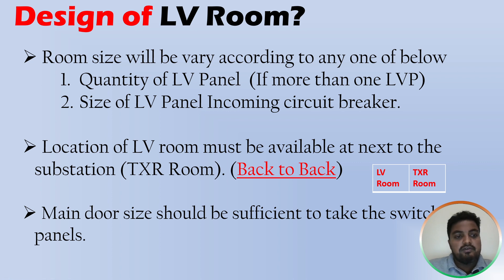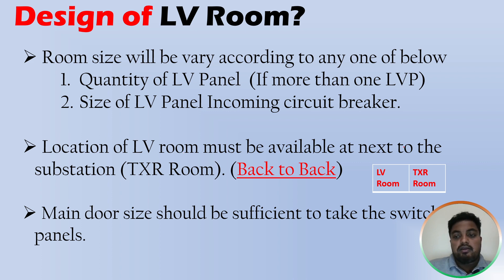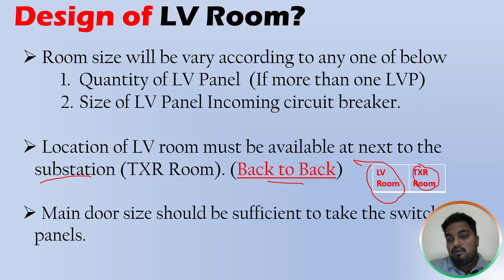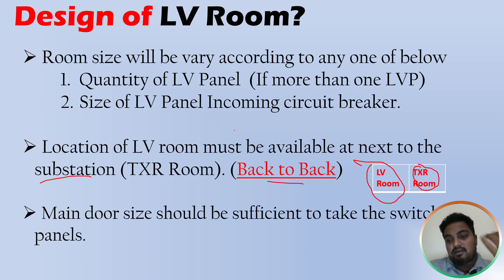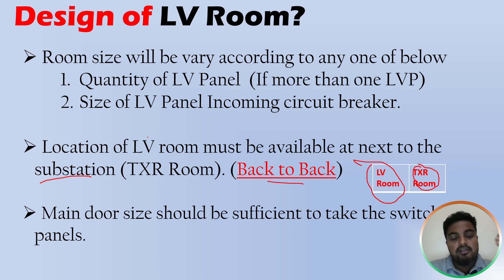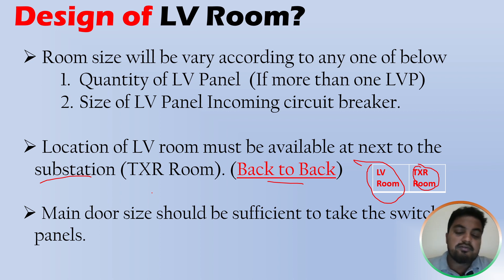Another key point is the location of the LV room — it must be located next to the substation, also called the transformer room. We place them back to back because the cable from the transformer feeds the LV panel and we cannot run this cable over a long distance. The reasons are: first, cost, and second, it is not practical to run high-current LV cables long distances. Locating the LV room adjacent to the transformer is both cost-effective and operationally simple.